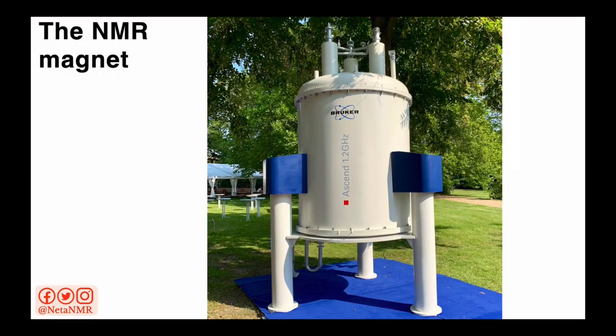In research labs, we use magnets similar to the ones used for MRI, but with a few differences. And before we get into those differences, I should clarify here that in order for these magnets to work, they should be inside a lab. Usually they're in the basement of a research building, and they should be connected to other electronics and to power supplies. Moving on to the differences between NMR and MRI magnets.